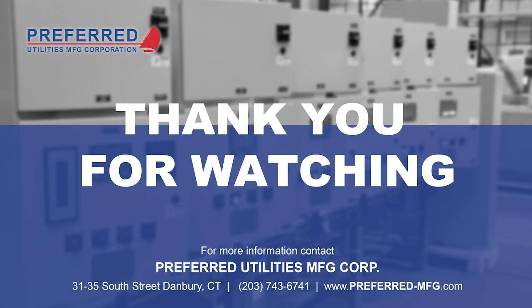In Los Angeles, there's a city code that says the maximum size day tank you can have is 60 gallons. So you pair a 2 or 2.5 megawatt genset with a 60-gallon day tank, and you're going to be burning almost all hot fuel coming back from the generator. And LA gets really hot too, inland. So a lot of times what we'll do in Los Angeles is, instead of the genset returning to the 60-gallon day tank, the genset returns all the way back to the main storage tank, so that we're not dumping hot fuel into that little day tank. And that way the generator is always getting cooler fuel from the main storage tank. But that's a really good question.